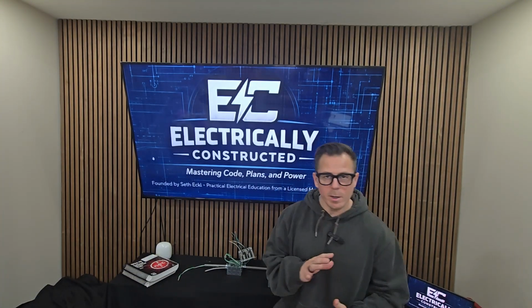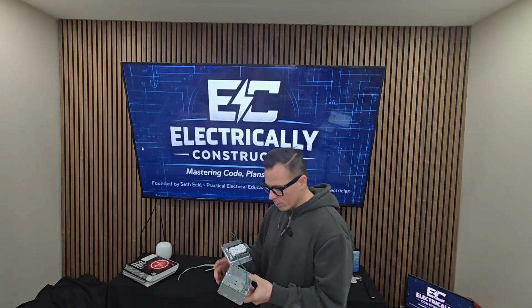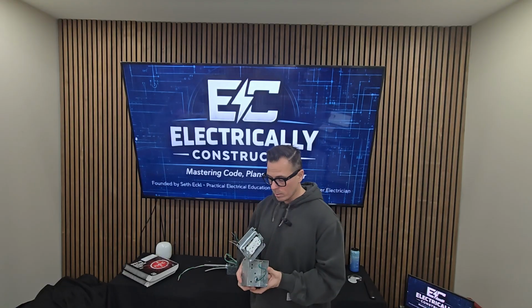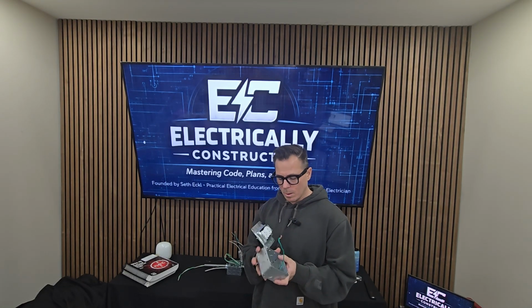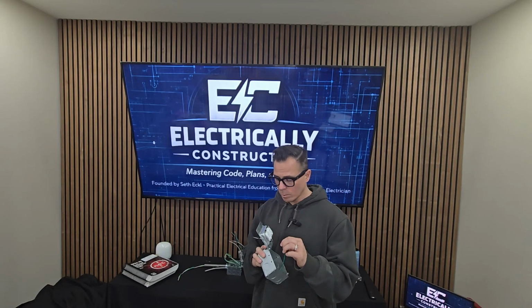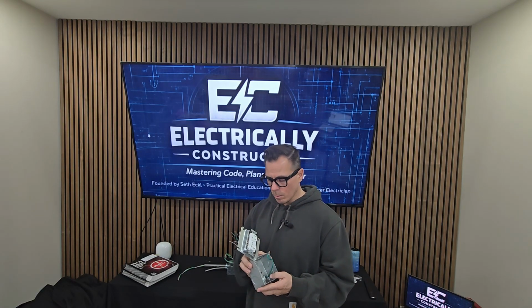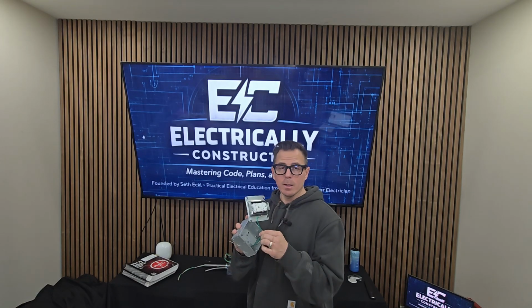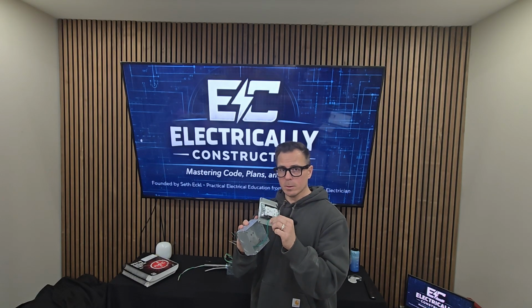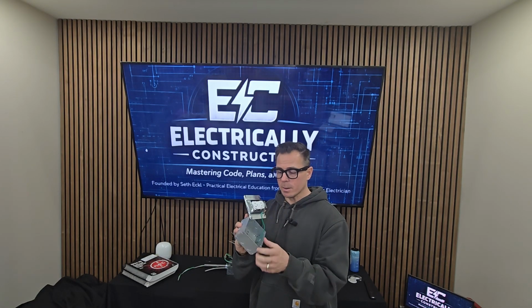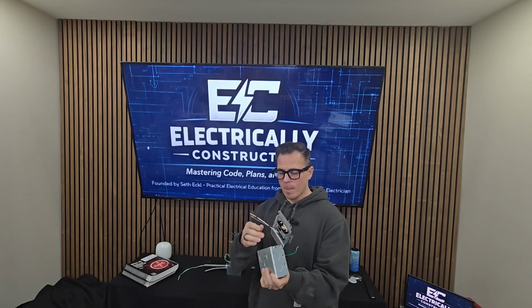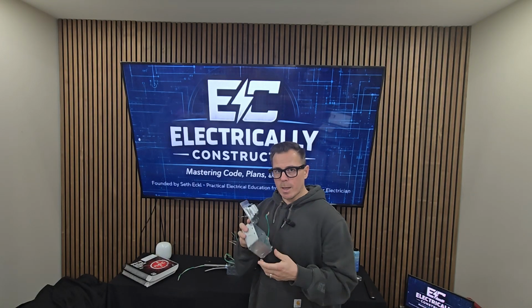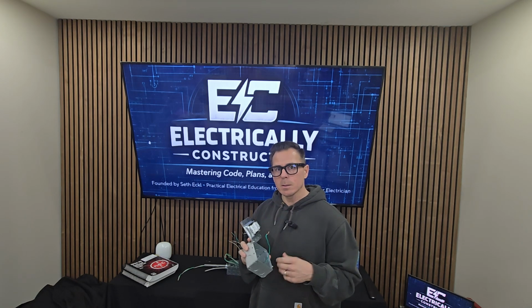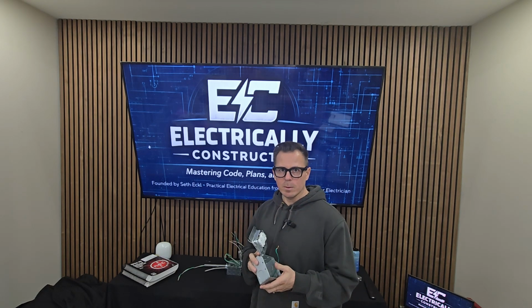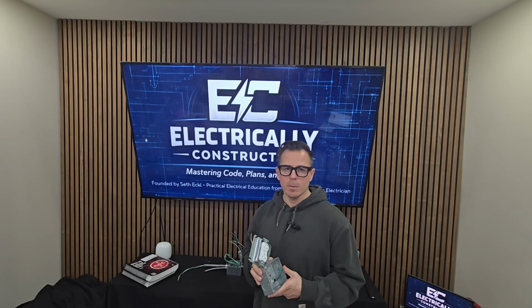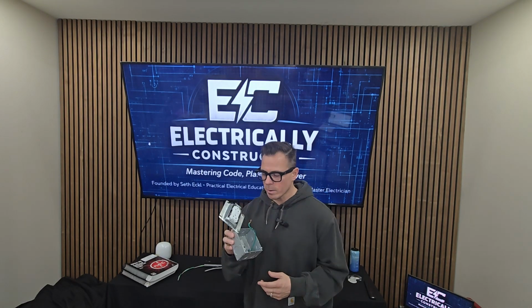Okay, so I wanted to pull in some of the rules that we talked about in the last video with the conductor fill rules. Some of them still do apply to the equipment grounding conductor fill. So one of the rules I wanted to point out is that if the grounding conductor originated in the box, meaning if it's screwed to the back of the box, or if it's a pigtail on a device, it does not count towards the box fill. It has to be entering the box or leaving the box, but however you want to look at it, that's how you're going to add that into your box fill calculation. So that's one of the things I want to bring up.